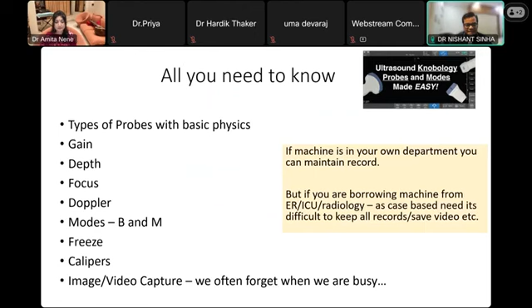Yeah, so basically there are 3 probes which we use. One is called linear probe, another is curvilinear probe, other is phased array probe. If you see on the right side of this screen, there's a graph where on the y-axis you are seeing penetration and resolution, and on the x-axis the frequency of the probe. Phased array probe has a frequency of 1 to 4 megahertz, where it penetrates a little more than curvilinear and linear probes, and it also has lesser resolution. But as you increase the frequency, the resolution increases but penetration decreases. That's the basic of ultrasound, and this is what you have to remember in your work.